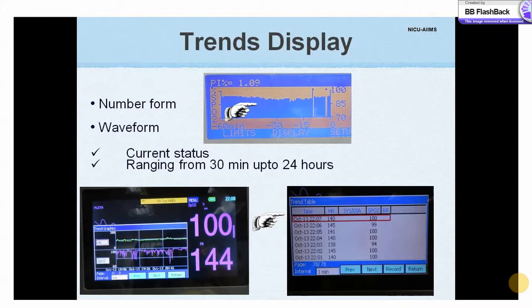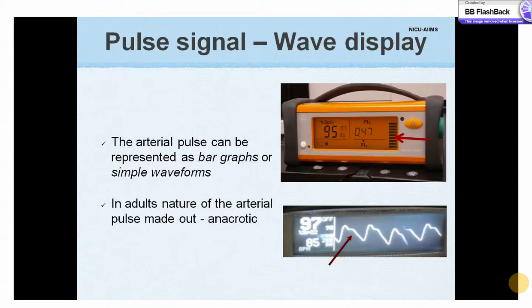The display style can be changed from the plethysmographic waveform to simple number format. The trend over 30 minutes up to 24 hours can be viewed as waves or bar diagrams, and trends can also be represented in the form of a table. The arterial pulse can be represented as bar graphs or simple waveforms. In adults, the nature of the arterial pulse can easily be discerned, which is usually anacrotic with a clear notch.